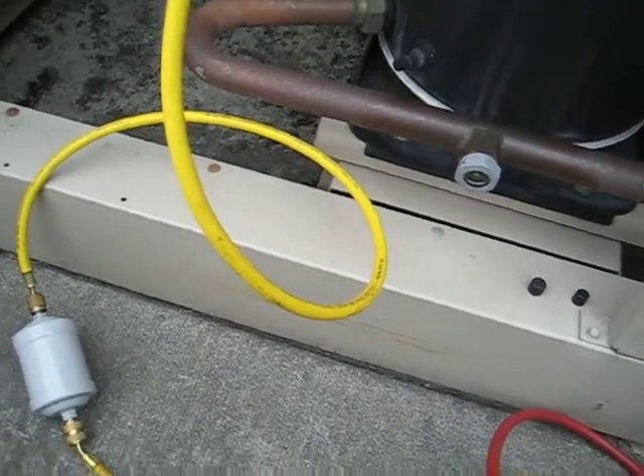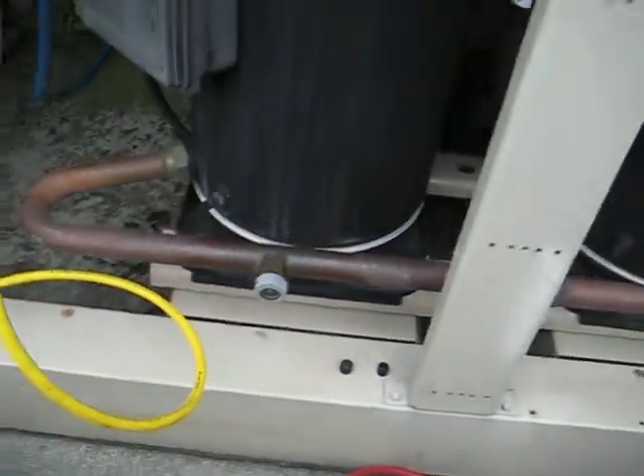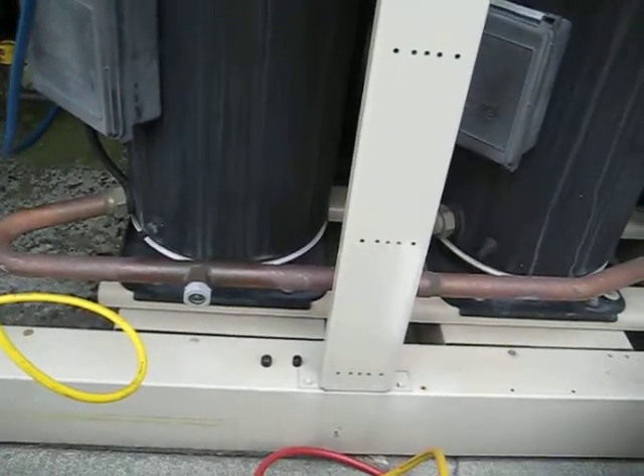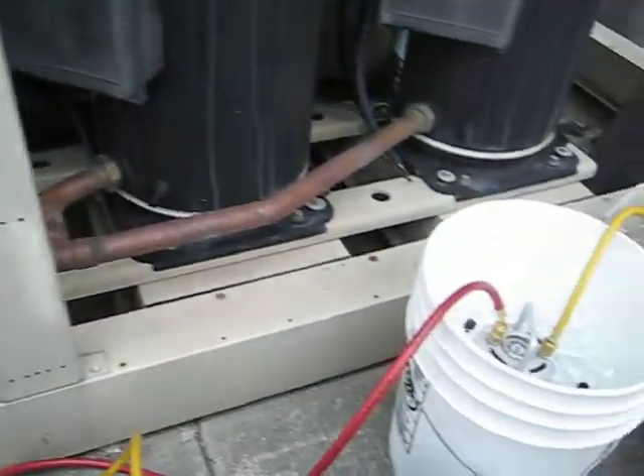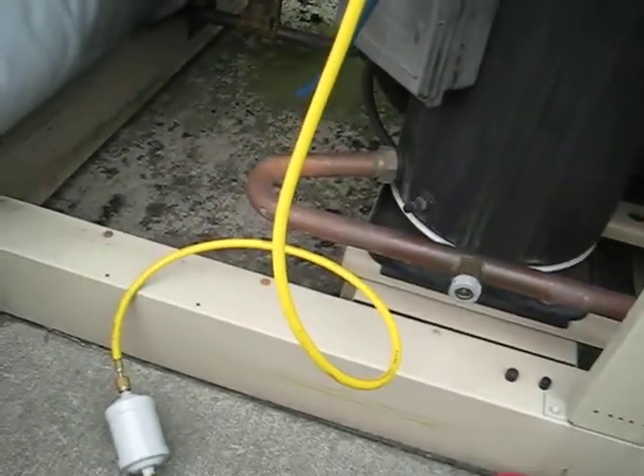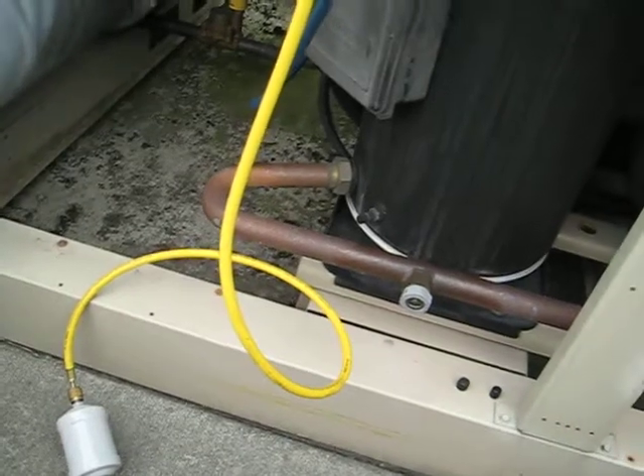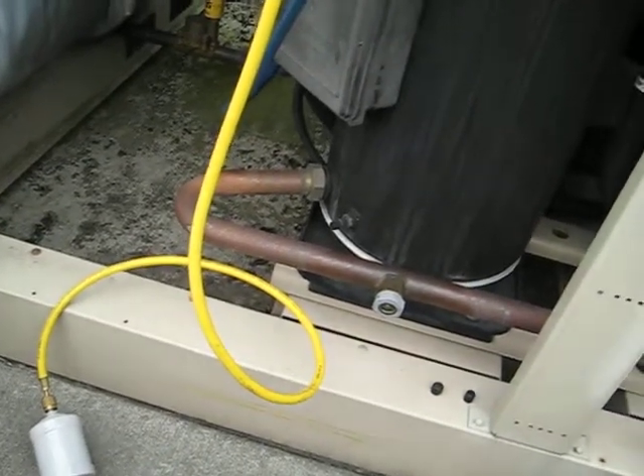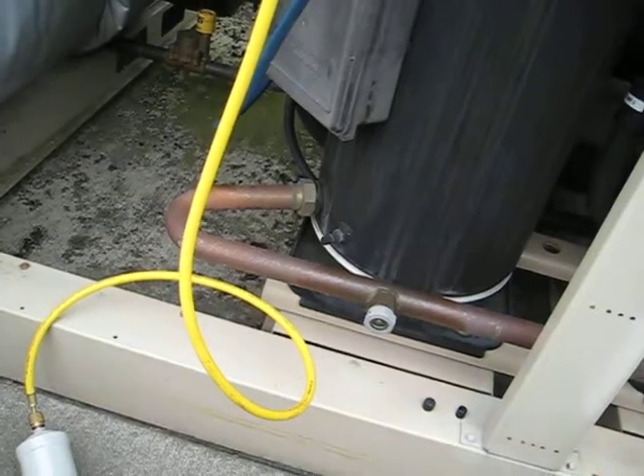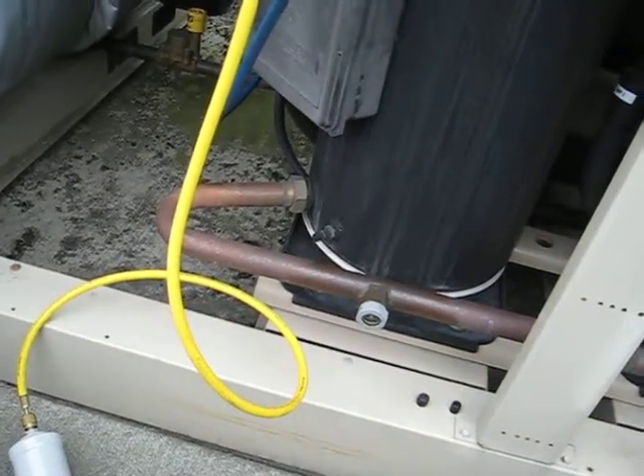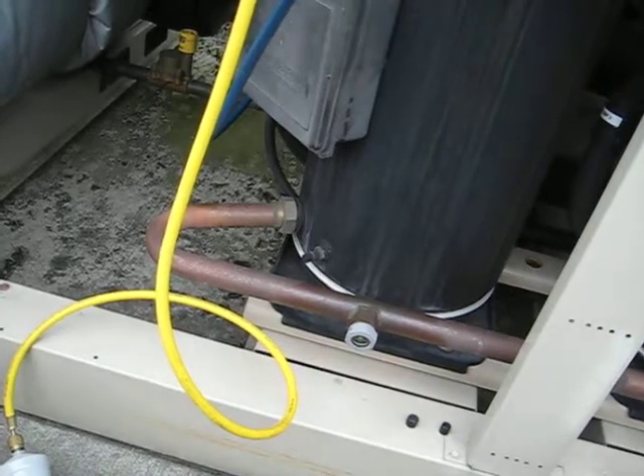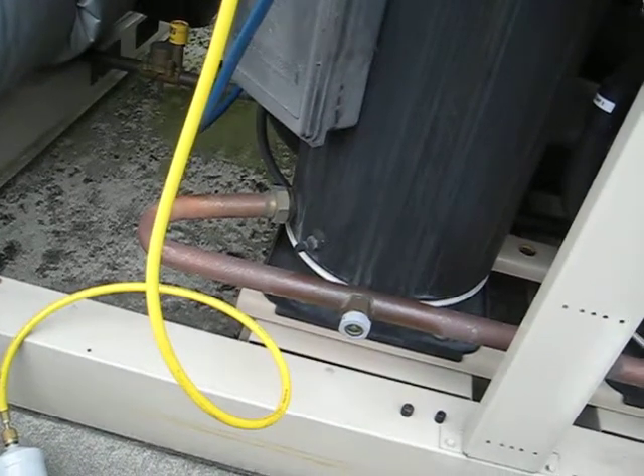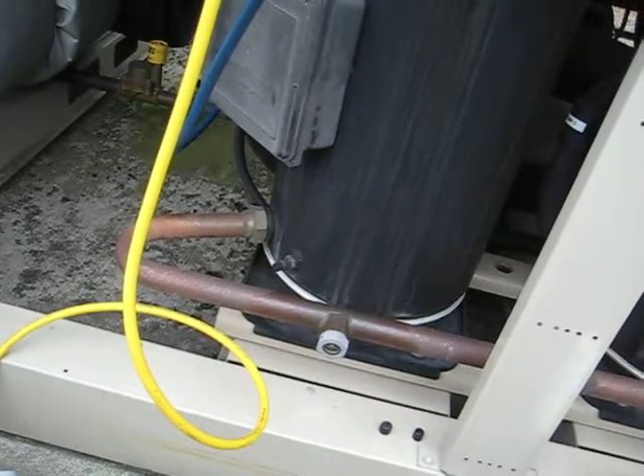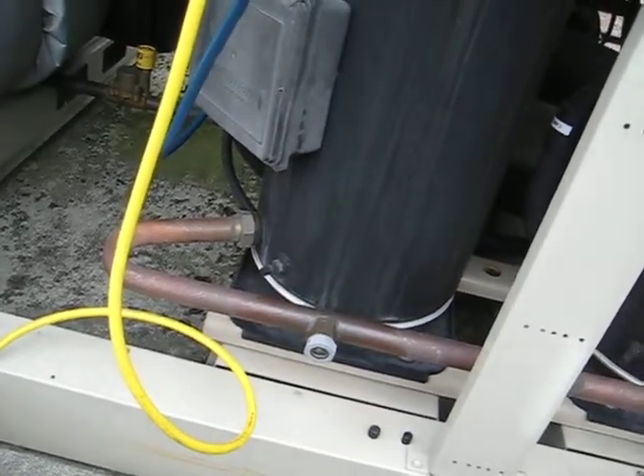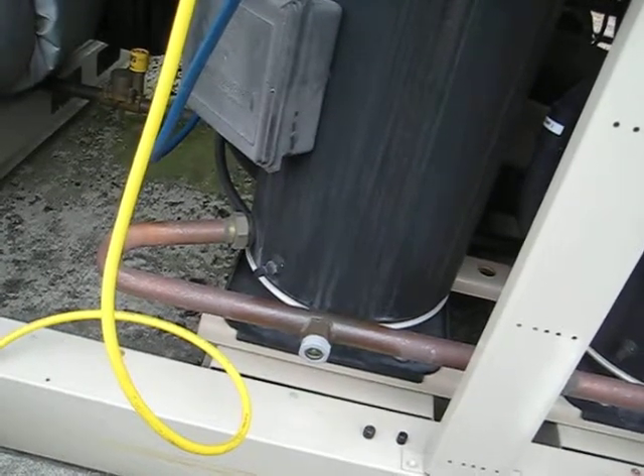So that tells you if you have a leak, if it keeps going up. Sometimes they have a little ball valve, and they'll even tell you to make sure you open that ball valve halfway, because it could have some gases trapped in there, then close it or fully open it. Also the refrigerant could be in the oil, and the compressor could be boiling off moisture in there. If you ever have a leak on the low side, you're going to suck air in, which could bring in moisture. R134A, for instance, has polyol ester oil, POE oil. It's hygroscopic, it attracts moisture.